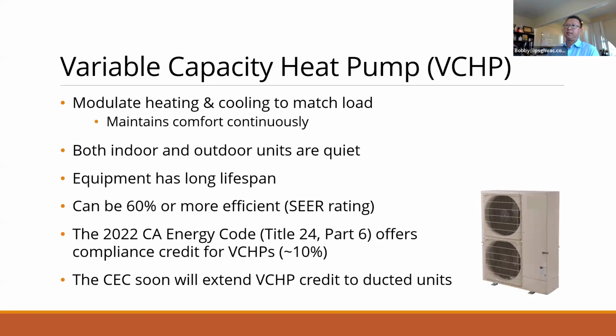Next slide, Nick. Okay, if we're going to take away one term, for me it's going to be variable capacity heat pumps, VCHP. You'll see it mentioned quite a bit in Title 24, especially going forward, modulating the heat from heating and cooling to match load. I'm not sure if everybody quite understands that, but what that means is basically the compressor, the engine for the condensing unit, modulates. So it's variable capacity. In other words, if you compare it to an accelerator in a car, for instance, if you need to go faster, it goes faster. If you step on an accelerator, and if you back off, it backs off.